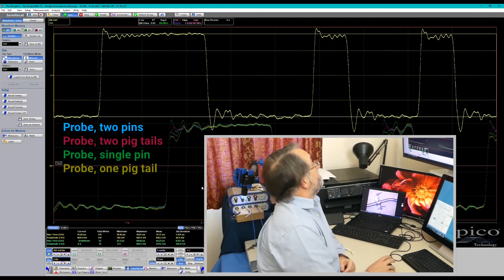And there we go. So I can let you run through those yourselves, but we've got amplitude and rise time in each case there. You should see that the amplitudes are about 859 millivolts on the through line at the moment. And what have we got? 851, 851, 800, all well within specification there via the probe. And the probe, of course, is compensated for its divide by 5 ratio.